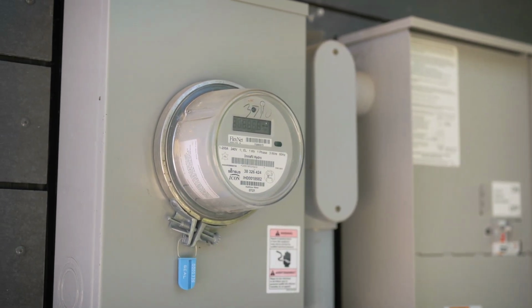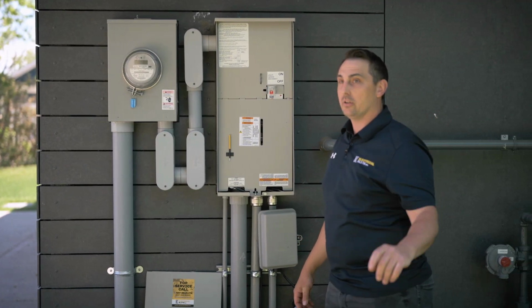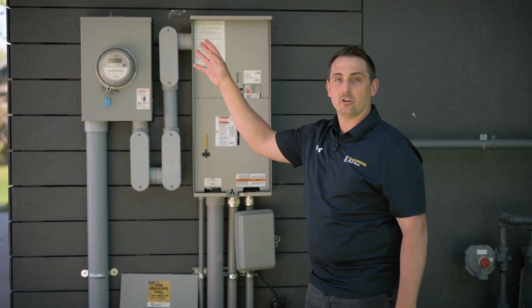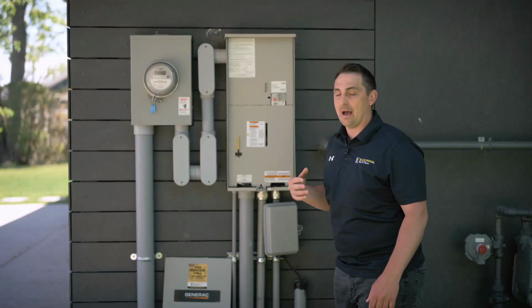If for some reason the generator is powering your house, but you notice that the street lights are on, or your neighbor that doesn't have a generator has power, come out to confirm that the utility power is back on. That may mean that you have an issue with your transfer switch and it's not functioning properly.